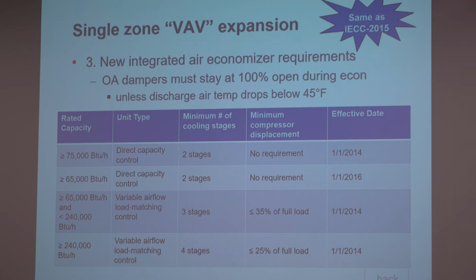And economizer mode is, of course, when you bring enough outdoor air in to offset the cooling load without turning the compressor on. There's an integrated mode where you do as much cooling as you can with outdoor air, and then you can kick on the compressor for the last little bit. Well, what happens in unitary packaged equipment is that if the compressor's too big and it kicks on, the controls of the unit can what's called dither the damper, and they'll close the outdoor air damper to sort of false load the compressor to keep it from cycling or to keep it from overcooling the discharge air. And so that became another way that economizers failed, because the actuators on the dampers were constantly opening and closing, but it also led to energy waste.